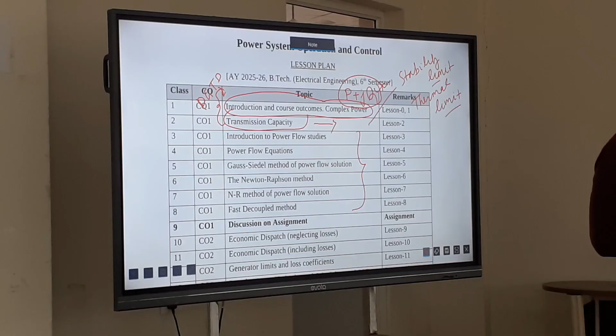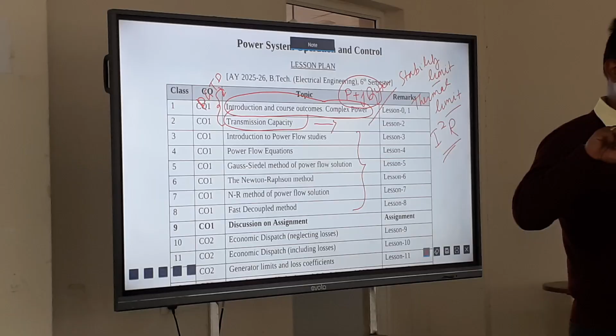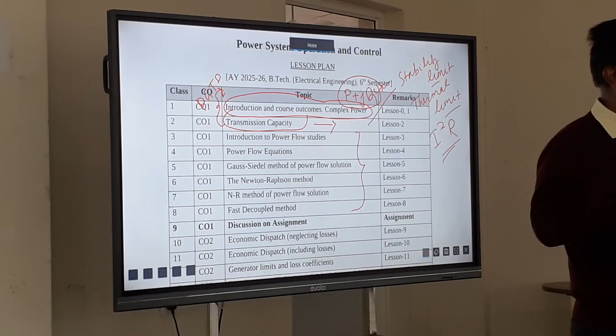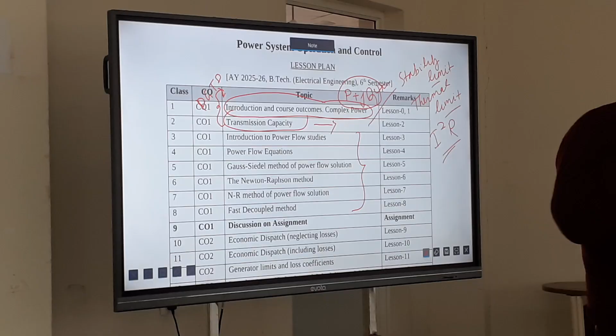Because of the I square R losses, heat is generated. Because of the heat, the transmission lines may expand, so they may permanently sag. Okay. Burning out a transmission line is a very remote possibility, but before that, permanent sag will occur. When sag occurs, the transmission lines may touch some object below it, leading to a fault. Okay. So we don't want to go to the thermal limit. It's a maximum capacity. The transmission line, we don't reach that. Okay. We are mostly concerned about the stability limit.